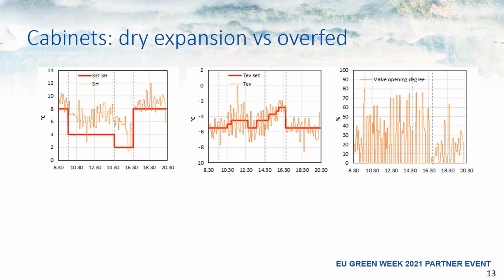We want also to show you what's the effect of the superheating on the performance of the system. This is an experiment that we have carried out during a winter day in Trento. What we have exactly done is decreasing the superheat, which was initially at 8 degrees. Here you can see the set of the superheat, and we have decreased it to 4 and then down to 2 degrees and then back up to 8 degrees. At the same time, we have progressively increased the evaporation temperature. You can see the set, it's this red line. And we have also measured the valve opening degree.